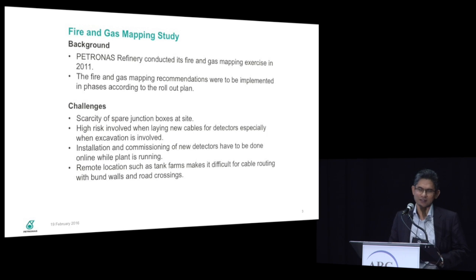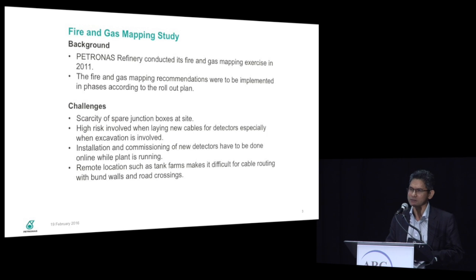During the project, gas detectors were installed based on the project rule of thumb. But over time, you must revisit the adequacy of the installation based on a scientific model, based on quantitative risk assessment, and that will give you a more accurate installation of the gas detectors so that your plant can be operated safely and reliably.